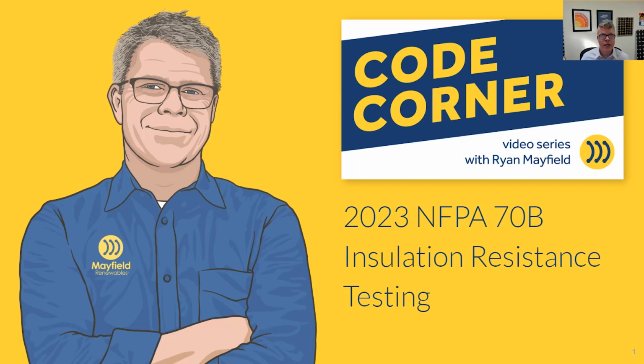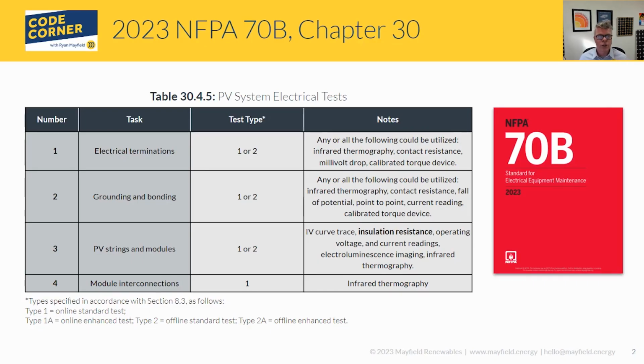And the thing I'm going to talk about here today is insulation resistance testing. First off, let's talk about Chapter 30 in 70B. This is where you're going to see the table for our requirements, the PV system electrical tests that they lay out. Today we're going to be looking at PV strings and modules and this insulation resistance. In the table, they've listed out different tasks, different test types, and different notes on those. That's what we're going to be focusing in on for this conversation. There are multiple tests that you have to do, so we can talk about those in future Code Corners as well.